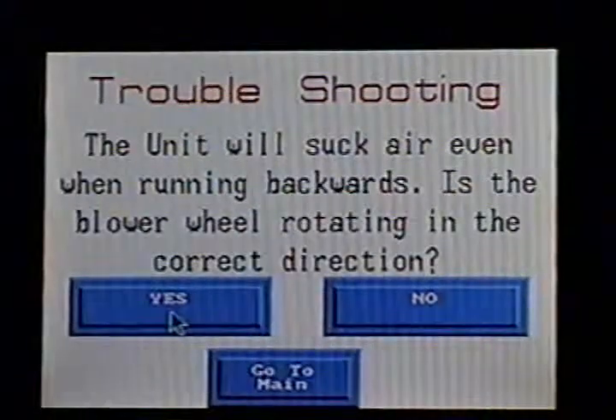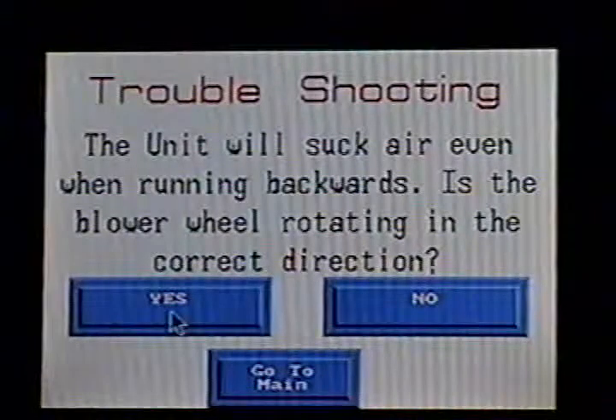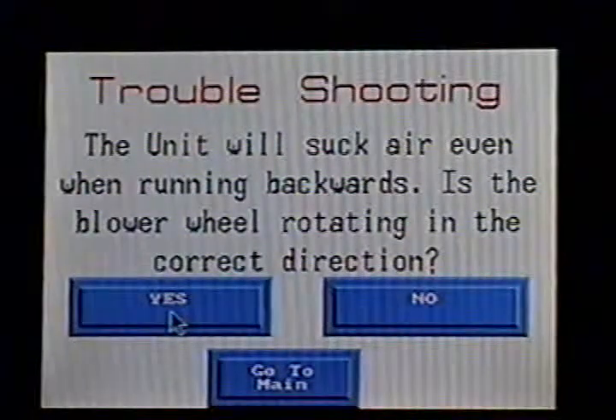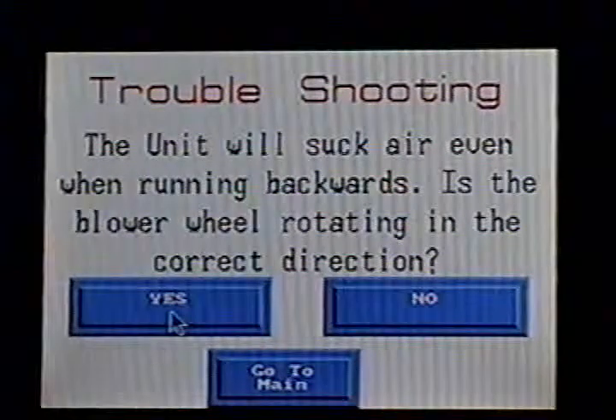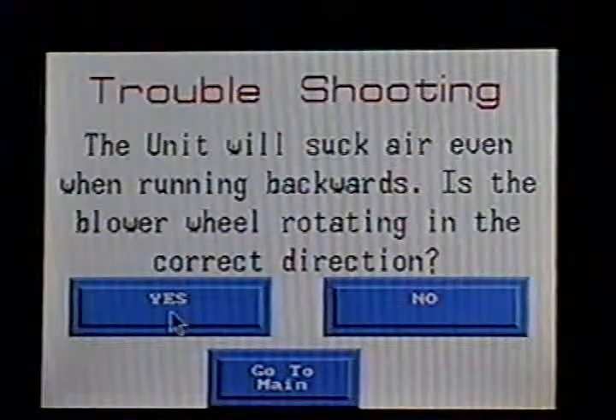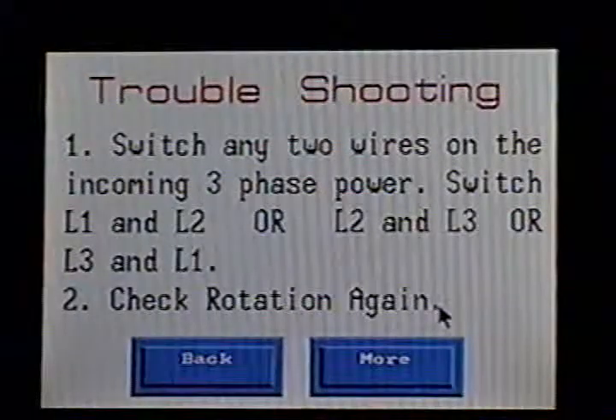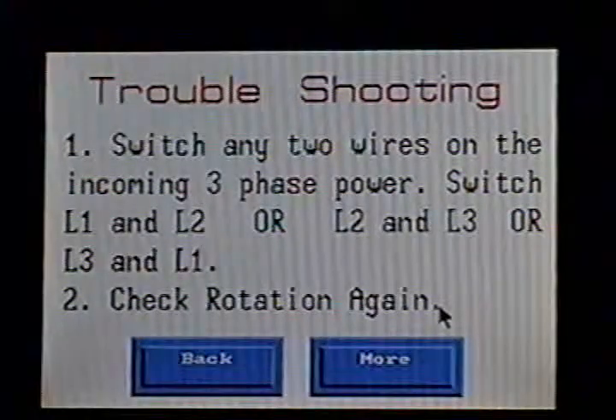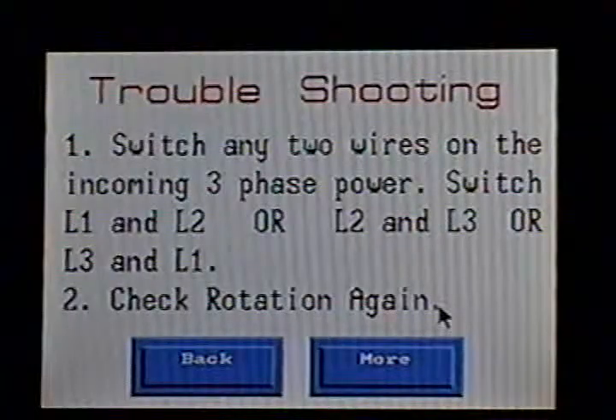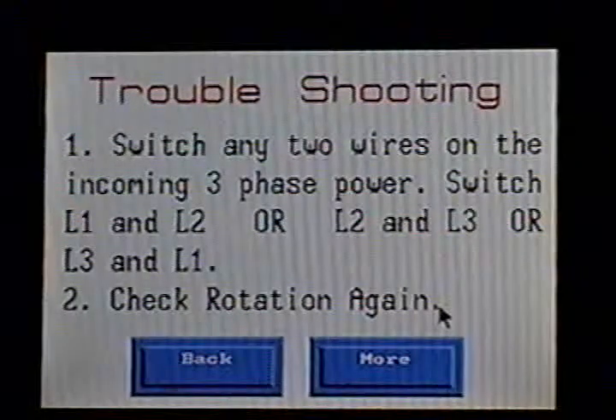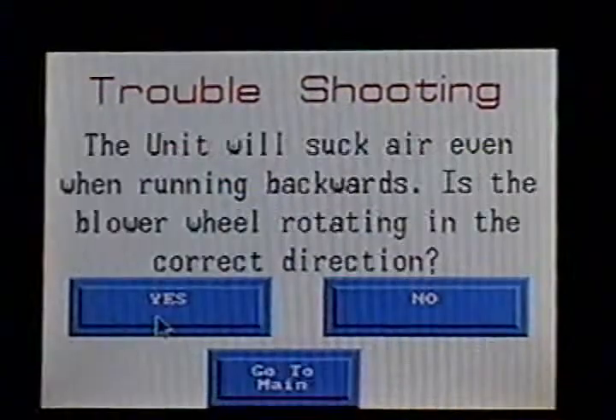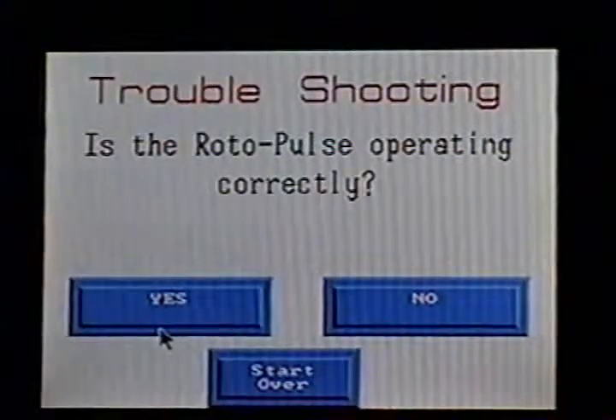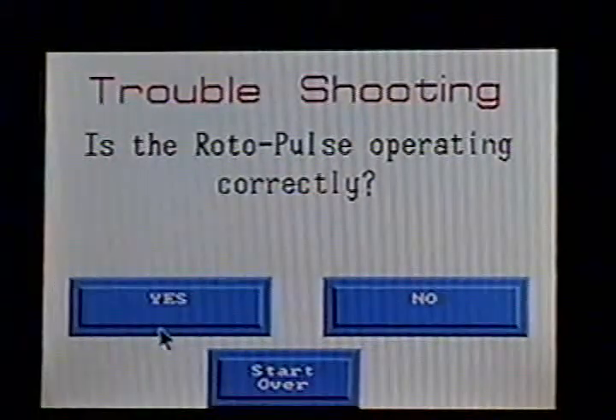Yeah. The unit will suck air even when running backwards. Is the blower rotating in the right direction? And that's in there twice because you always get the wrong answer the first time. Because they say, of course it is. Okay? No. Switch any two wires. It gives you some brief instructions on how to fix that problem. Okay? We'll go back. We'll say, yes, it's running correctly. Yes, it really is. Is the Roto-Pulse operating correctly?